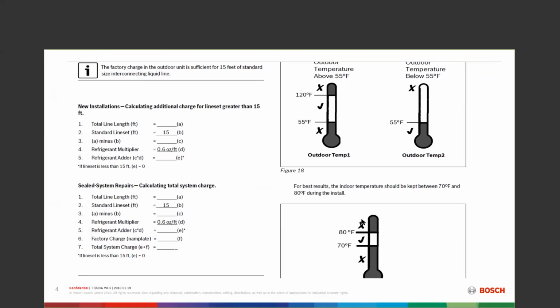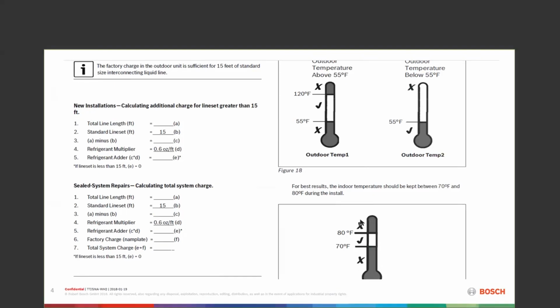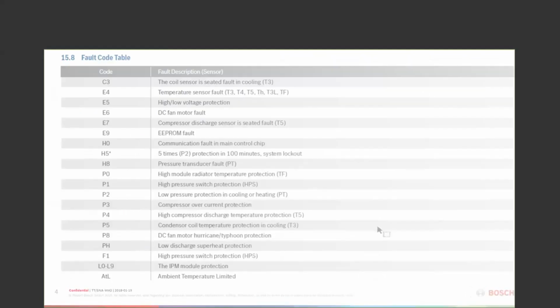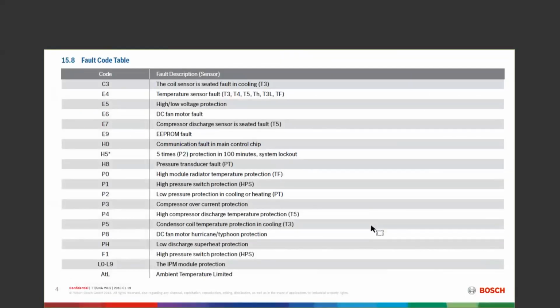You're just going to pull 350 micron vacuum, open up the suction side service valve first, and basically what we would call dump the charge. But this particular machine, again, critically charged. So you take the 15 that we give you, you take number 3, and you're going to multiply number 3 by number 4. So we're looking at 0.6 ounces per linear foot. Weigh that in with a very good weighing scale. We're not doing a sweat bag type situation. We need a precise measurement of refrigerant going into this machine.